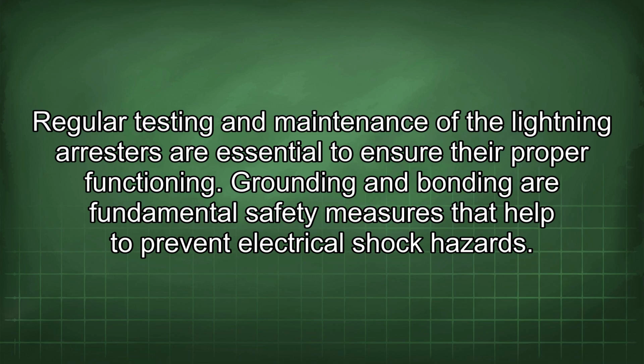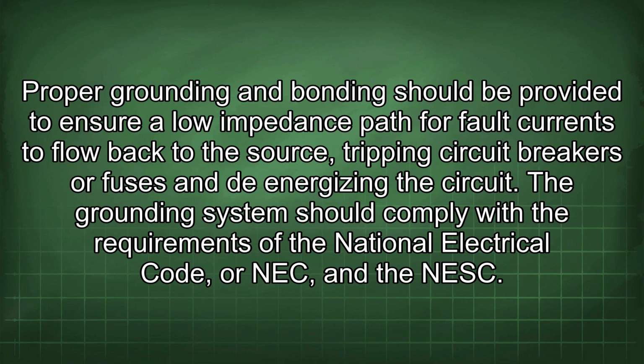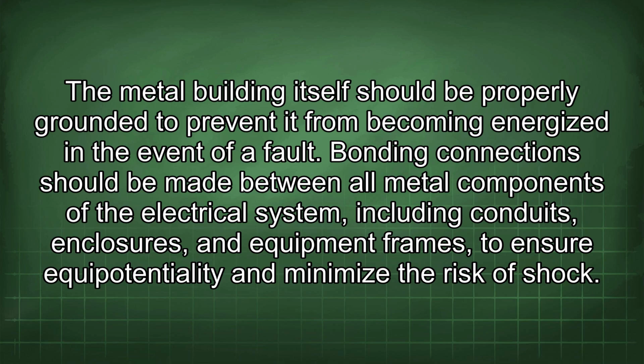Grounding and bonding are fundamental safety measures that help to prevent electrical shock hazards. Proper grounding and bonding should be provided to ensure a low impedance path for fault currents to flow back to the source, tripping circuit breakers or fuses and de-energizing the circuit. The grounding system should comply with the requirements of the National Electrical Code, or NEC, and the NESC. The metal building itself should be properly grounded to prevent it from becoming energized in the event of a fault.